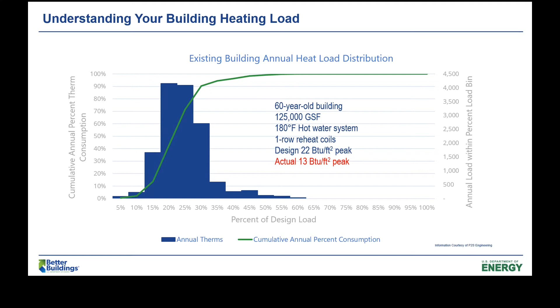Really think this through—if you don't have this kind of data, it's really hard to make that decision. Sometimes it's easy to collect: you can buy a little portable data logger or use an energy management system, put the data logger on an oil burner or gas valve, and just measure when it's operating.